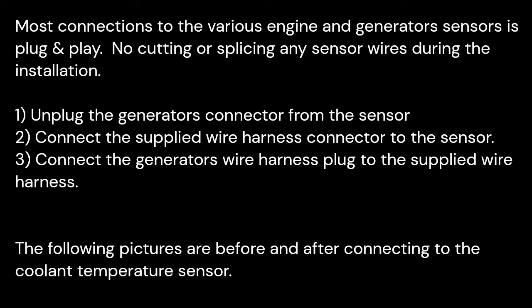Most of the connections to the various sensors in the generator are plug and play. No cutting or splicing of any sensor wires in the generator. The process of connecting the supplied wire harness is simply just unplug the existing plug from the sensor, connect the supplied wire harness connector to the sensor, and then connect the generator's sensor plug into the supplied wire harness. The following 2 pictures illustrate before and after connecting up to the coolant temperature sensor.